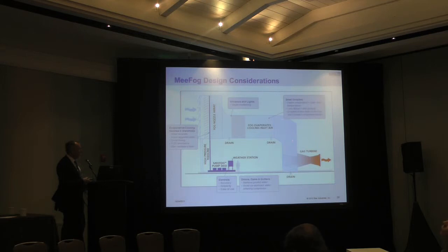And usually there's some water on the back wall here. We'll often have a channel that goes around the compressor, so any water flowing down this wall gets directed to the drain in the floor. And on some GE gas turbines, the distance from the floor here to the inlet is quite short, and the velocity is very high, so you can actually suction water up off of the floor. In that case, we use a little false floor there to direct water down the drain.